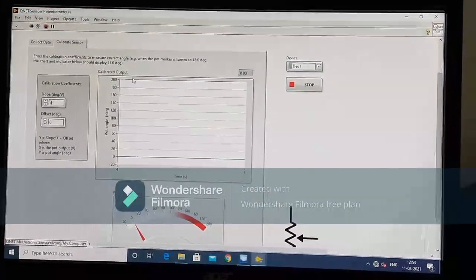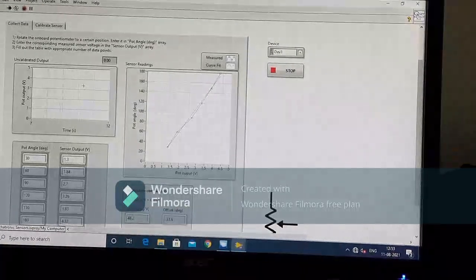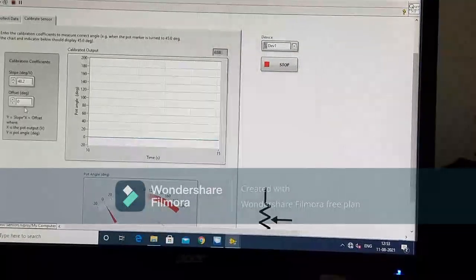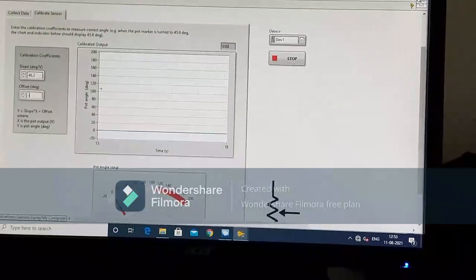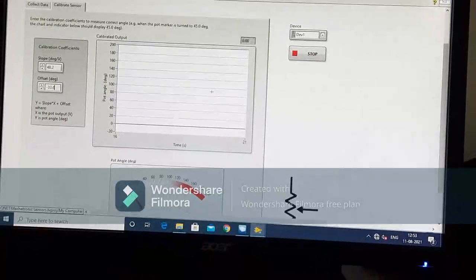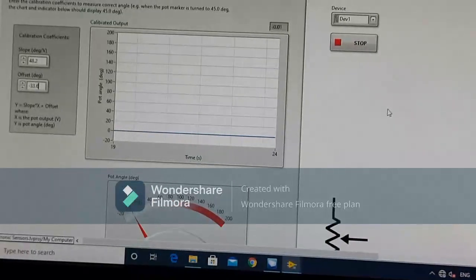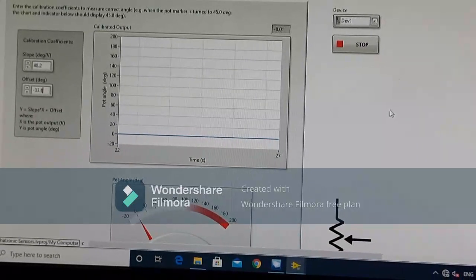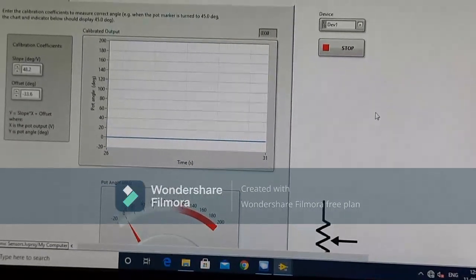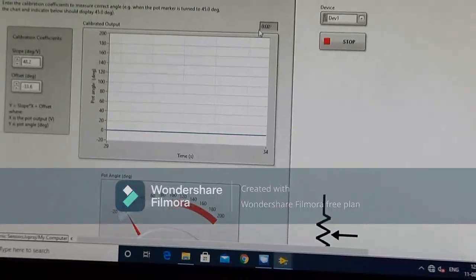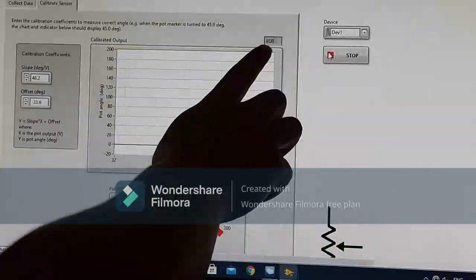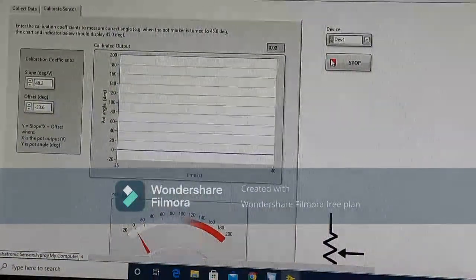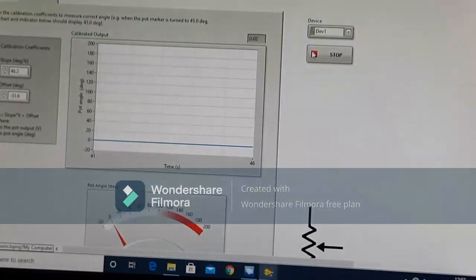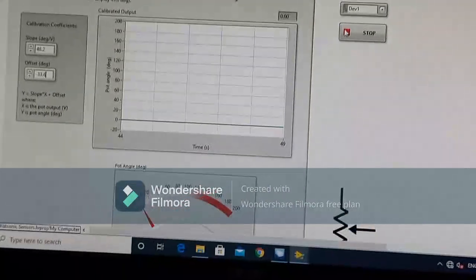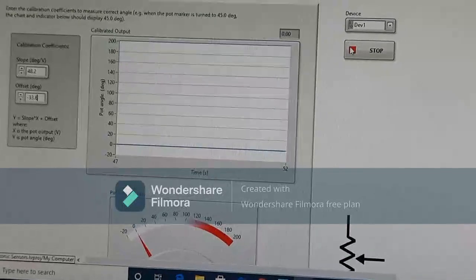I'll just place this data. The slope was 48.2, and let's check it, 48.2, and the offset is minus 33.6. Fine. So this is what I got here. I'll place the sensor in my board at a particular location so as to get the exact value in the calibrated output region. So this is the calibrated output region. Whatever value I put in my sensor board, I should get the same value in this part, the calibrated output part. This is the main objective of our experiment, to make the sensor calibrated.